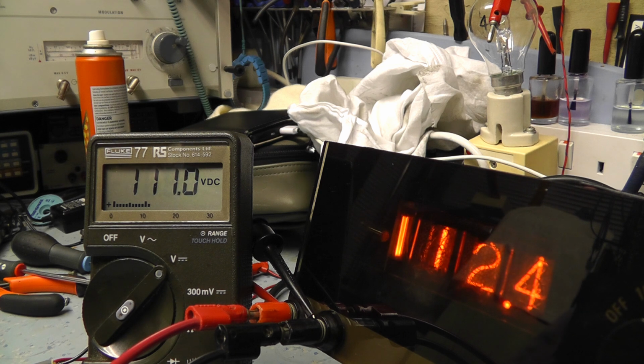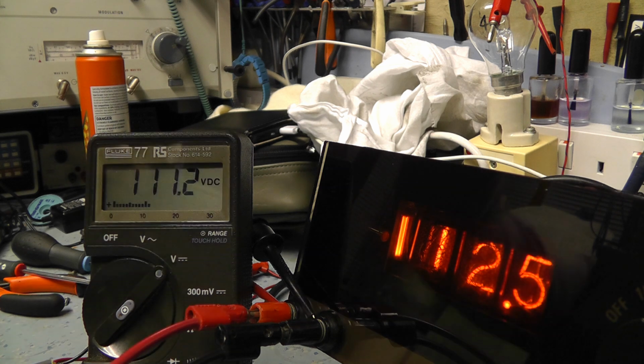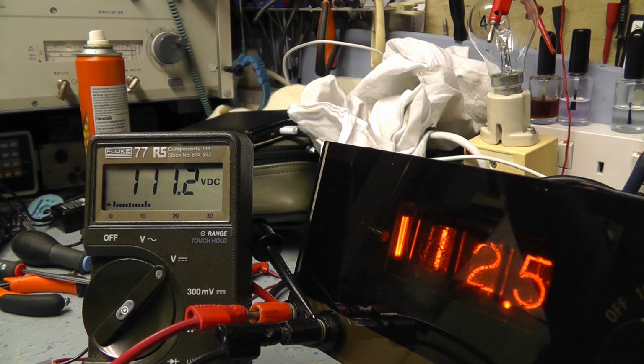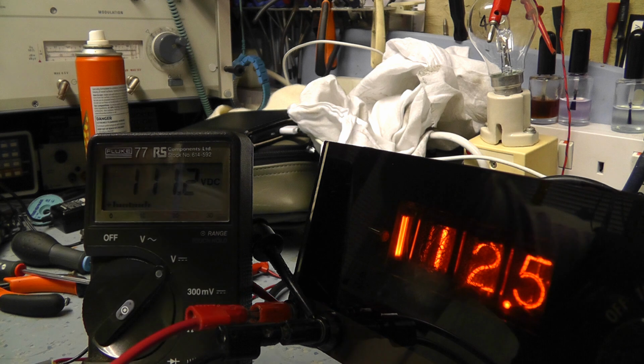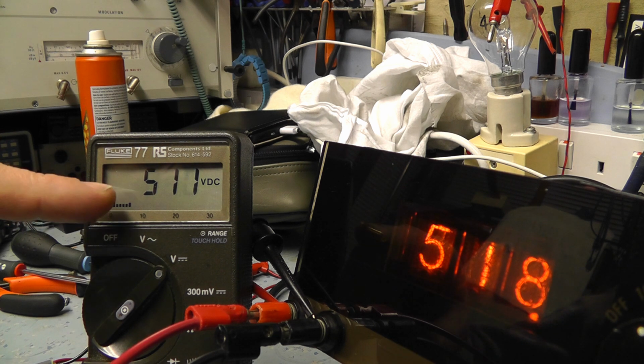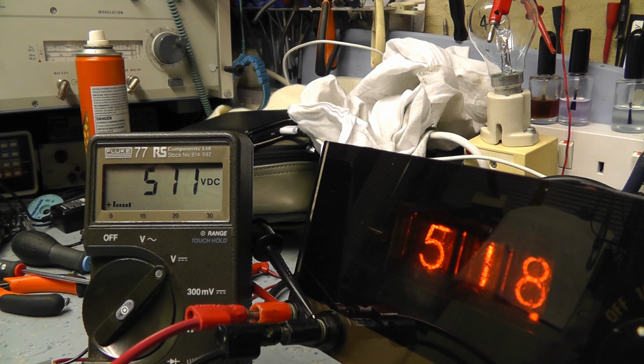So that's 111 volts, and you see we've got 112.2. As I say again, that's an adjustment on the attenuator, so I can bring that in. So I think I'll have to do that. I haven't adjusted that attenuator yet, and then we'll try the 1 kV range, and we'll put in 500, that should be 511 volts. Okay, and you can see here now it's quite a significant amount out. The Fluke showing 510 volts, and the Roband showing 518.